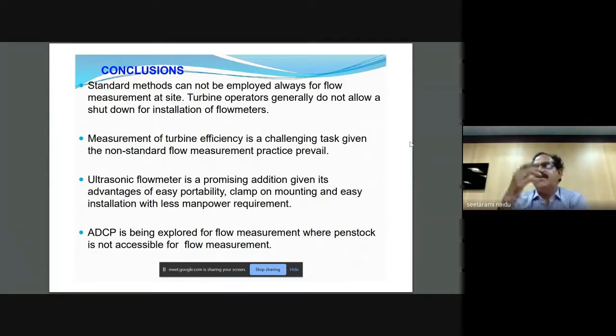Otherwise, current meters fitted inside the penstock were a good option, not today but 20 years earlier, because there is physical loss of water and power generation during shutdown, along with the difficulty of requiring many days for experimentation. I know of one situation where the Kerala government did not give permission to shut down for testing of a turbine at Lower Periyar. Such shutdowns, especially in summer seasons, are rarely allowed for investigation purposes, so ultrasonic flow metering is very handy.